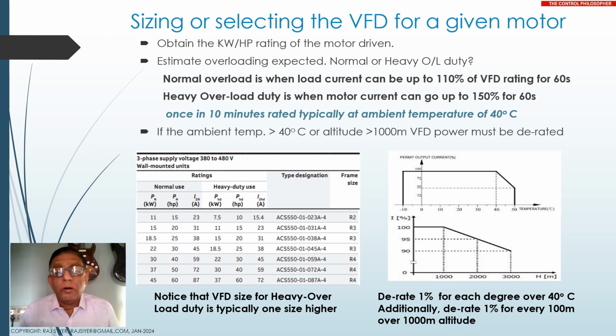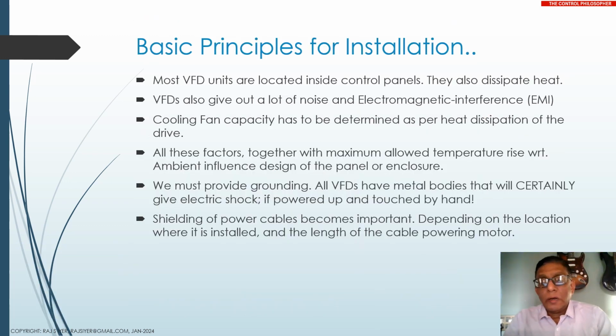Now this consideration of overload and derating for altitude, derating for ambient temperature should be done at the time of selecting the VFD for a certain application. And of course, the main consideration is the VFD should be the same as the power rating of the motor to be controlled.